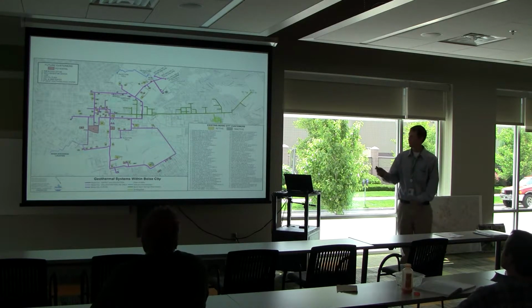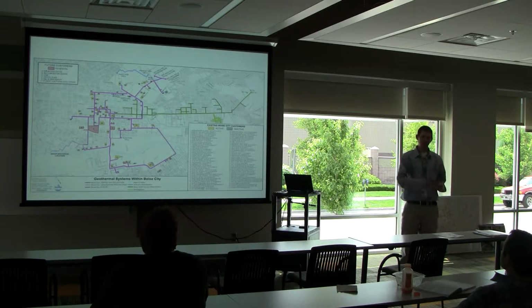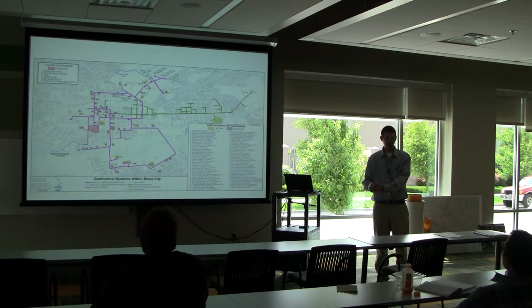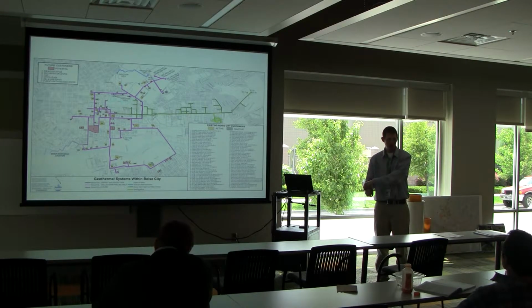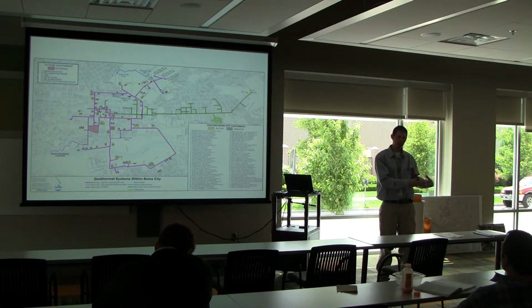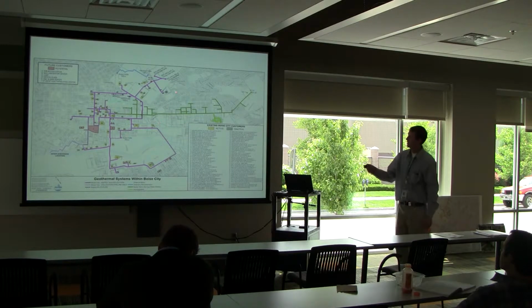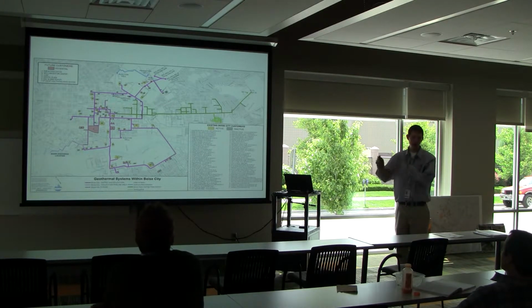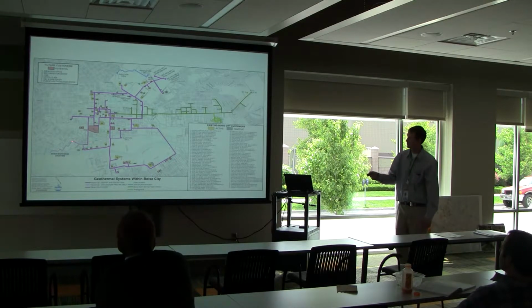So all of a sudden we've got a building wanting to use collection water, but not enough upstream users. So we have to artificially bypass water, called crossover, putting hot water into our collection line. It turns out I'm bypassing more water than I would ever be selling to this customer if it were a supply customer instead. I'm wasting this water just to keep the collection line warm. It doesn't make sense to put collection customers on this end of the system because there's just not enough demand upstream, and it doesn't make sense at the end of any leg either.